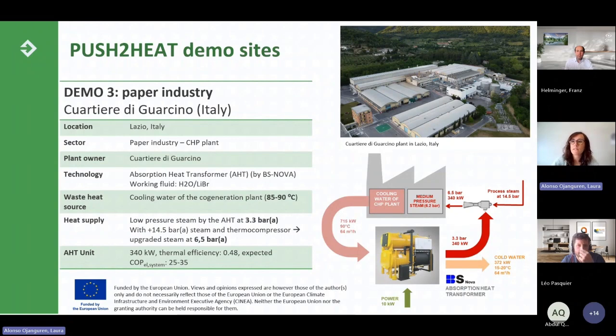And in this case, we are not talking about an electrical COP. We focus more on a thermal COP, which is around 0.5, and this is a typical level in thermally driven heat pumps.